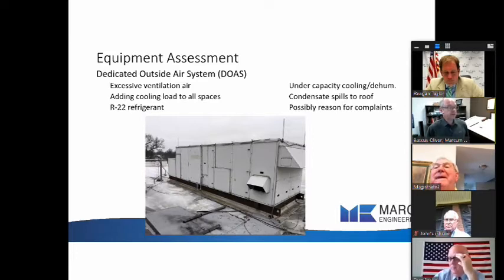What we found out about this unit is it's excessively ventilating. It's bringing in more CFM than is required for the building occupants. It's also under capacity on cooling and dehumidification. It cannot totally cool and dehumidify what it's trying to bring in. So thus, what it's doing is it's adding load to all of our spaces. I believe this unit right here is probably the chief culprit in our comfort complaints. When it's on and when it's running, it's overwhelming our individual spaces, HVAC units.